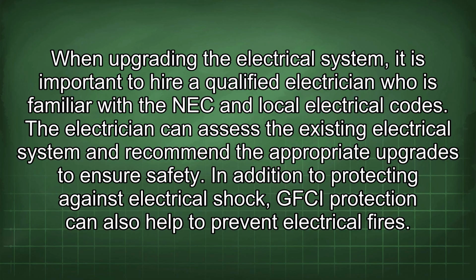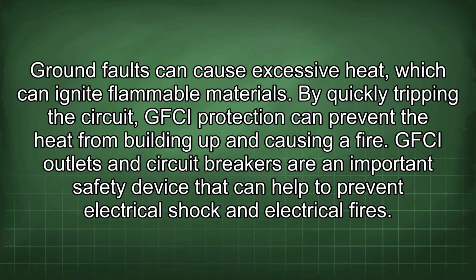In addition to protecting against electrical shock, GFCI protection can also help to prevent electrical fires. Ground faults can cause excessive heat, which can ignite flammable materials. By quickly tripping the circuit, GFCI protection can prevent the heat from building up and causing a fire.